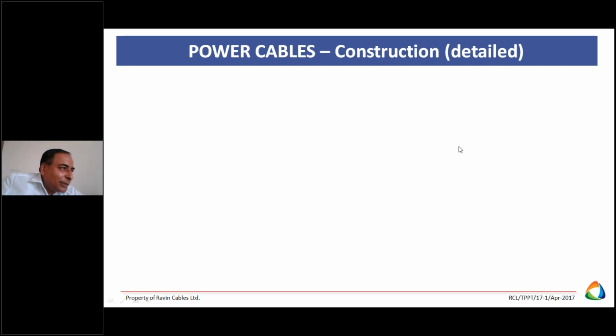But in the case of HT cables - 11 kV, 22 kV, 33 kV - you find round conductors instead of triangular ones. Why round conductors? Because if electrical field intensity is higher at one point, the insulation breaks at that particular point. To make a uniform potential surface over the conductor, we make a round conductor. Still, being a round conductor, on the longitudinal part some stretches or sharp points are there.